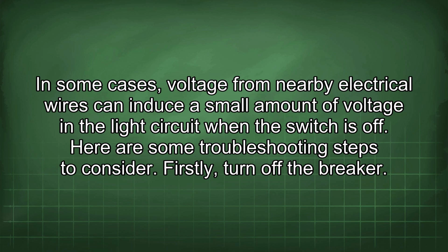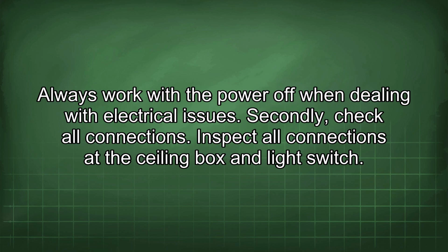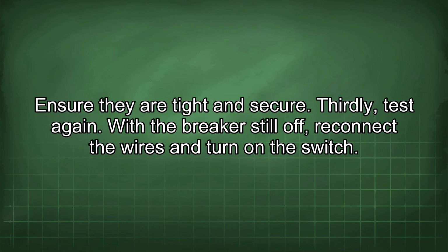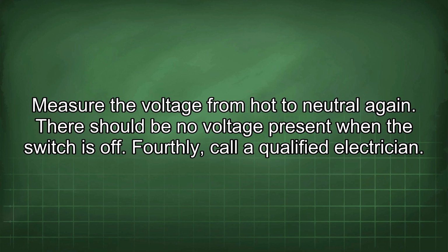Firstly, turn off the breaker. Always work with the power off when dealing with electrical issues. Secondly, check all connections. Inspect all connections at the ceiling box and light switch. Ensure they are tight and secure. Thirdly, test again. With the breaker still off, reconnect the wires and turn on the switch. Measure the voltage from hot to neutral again. There should be no voltage present when the switch is off.